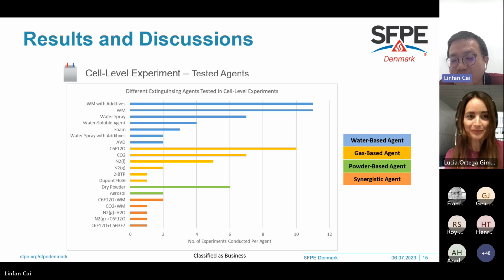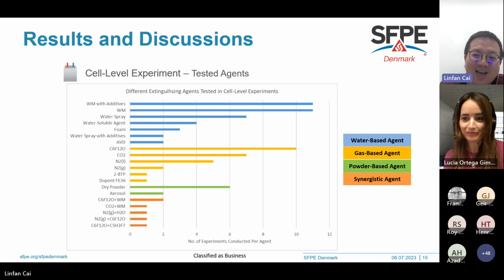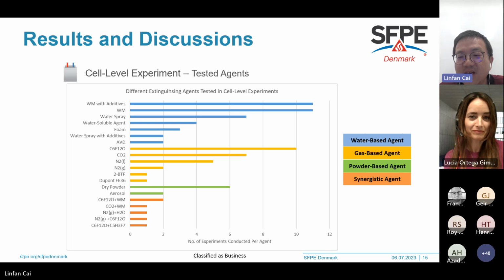The answer is yes. That's why in the conclusion I didn't say the sprinkler is definitely the answer - the sprinkler will definitely have the detrimental effect as you mentioned. But when water is mixed with additives, some of the additives will deionize the water mist. That's why if the water mist is deionized, it will have less detrimental effect on conductivity. This is what I found from the research papers.